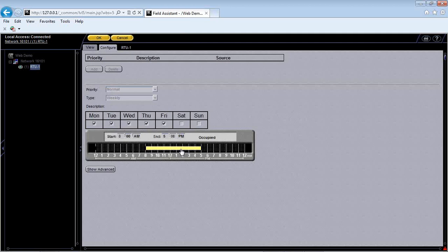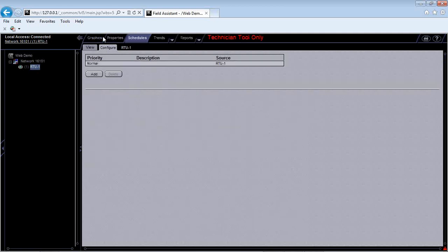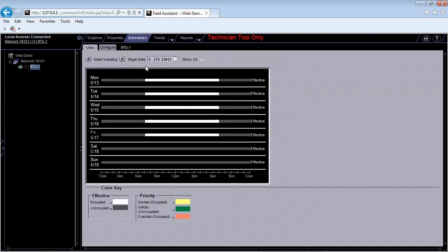So I'm from 8 a.m. to 5. If I click on this yellow bar, I can actually just drag it and my times will adjust, or I can just type in whatever times I want. So I want to go 7 a.m. to 7 p.m. You can see my bar got a little bit longer. I hit OK. Now I just entered a schedule. If I look on it, I will have a schedule for all of these days, right? White equals occupied, gray equals unoccupied.